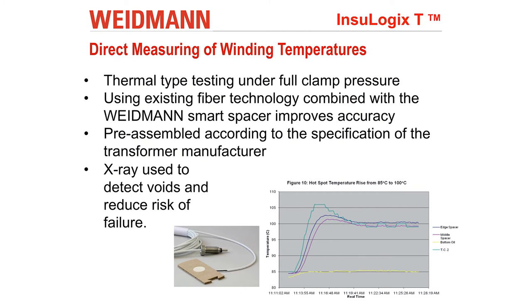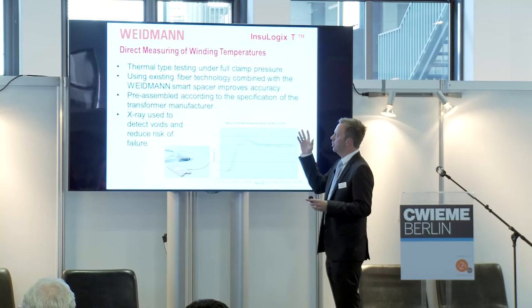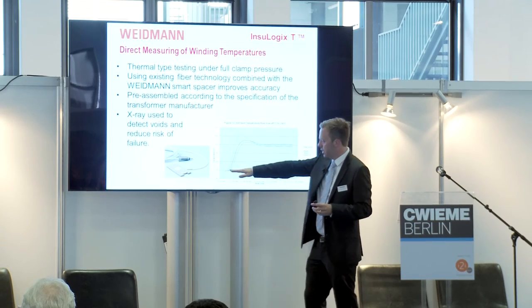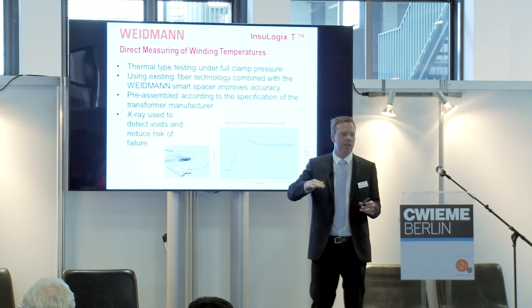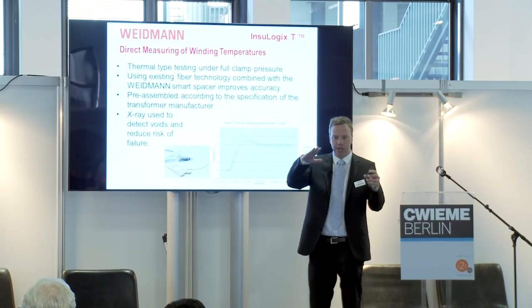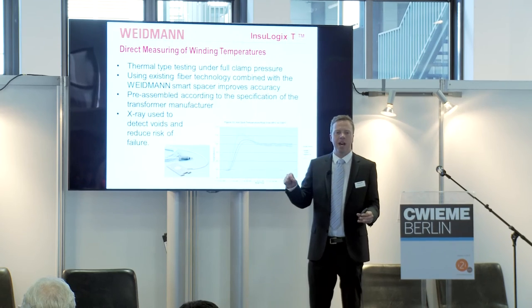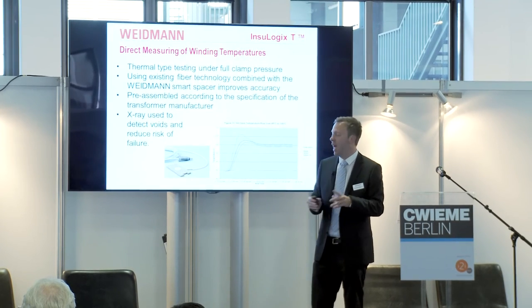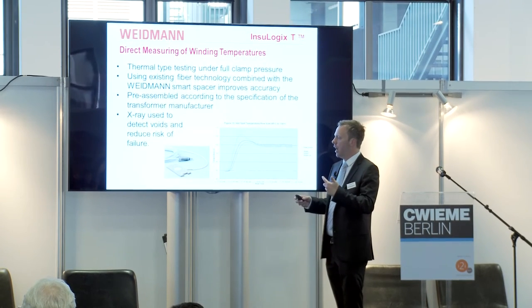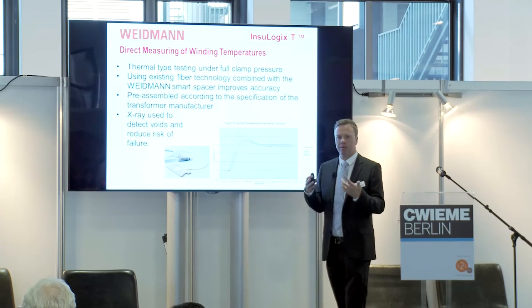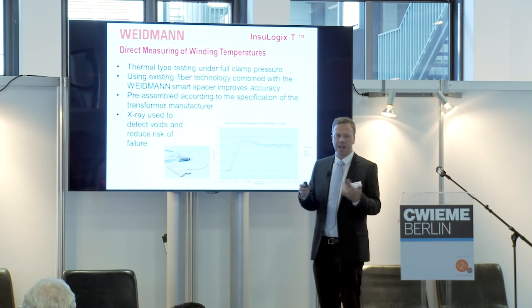So if we look first of all at the temperature monitoring: we basically take a spacer that you would have installed in your transformer package as normal in the winding, and we embed in that a fiber optic probe. And from there, we monitor the hotspot temperature of the transformer and provide that.